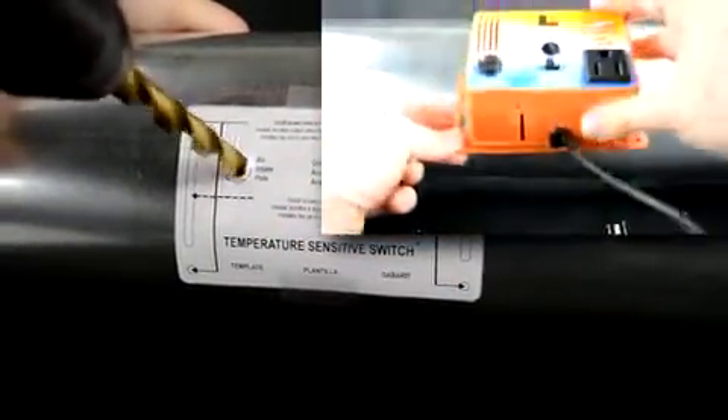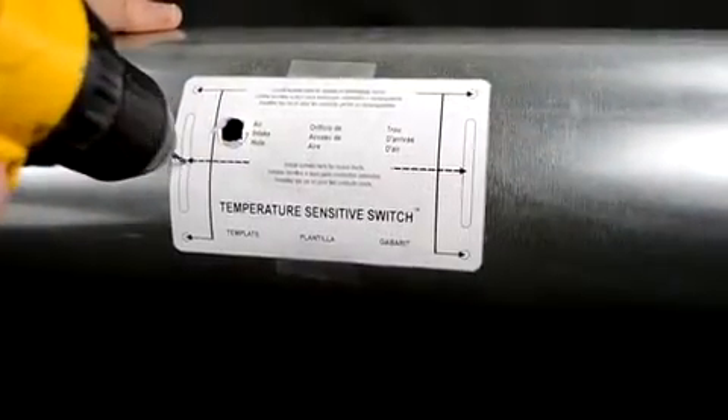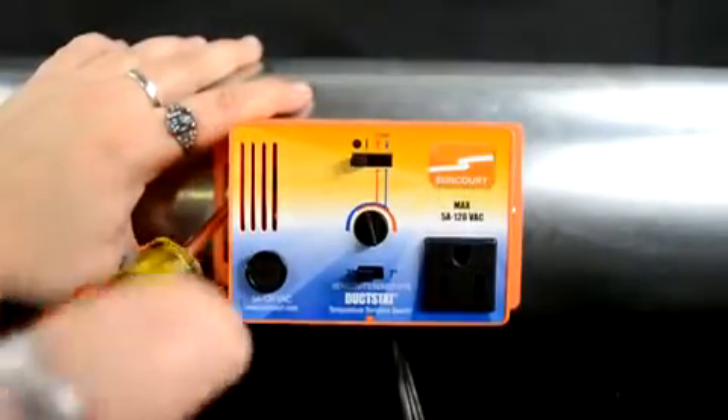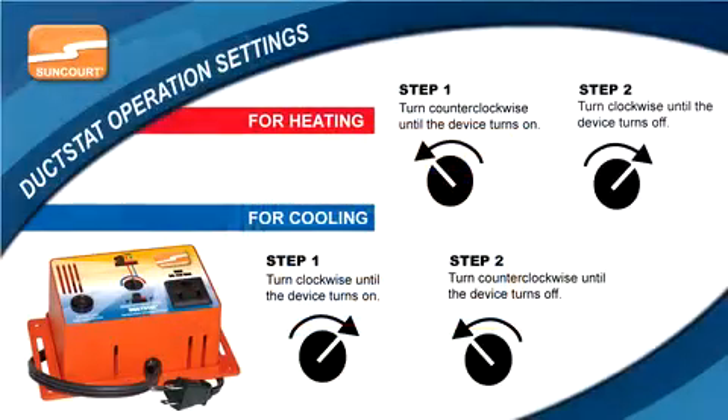This hole should be ½ inch in diameter. Drill mounting holes in the air duct to line up with the appropriate mounting holes located on the template. Tighten the supplied screws snugly in the appropriate placement for your ductwork. Do not over tighten. Follow the operation settings to adjust the Ductstat.